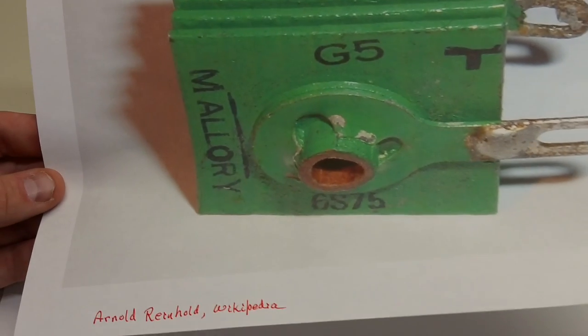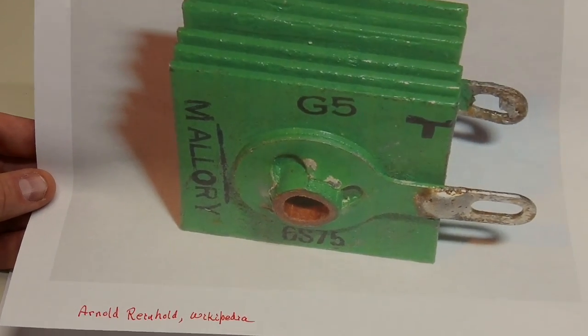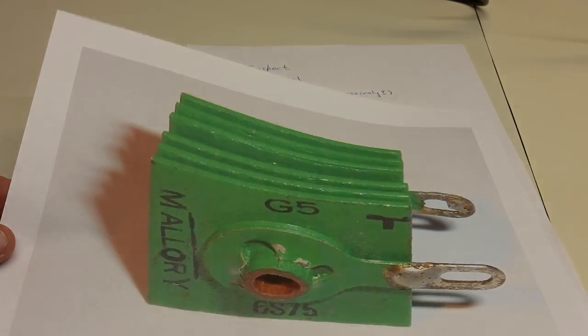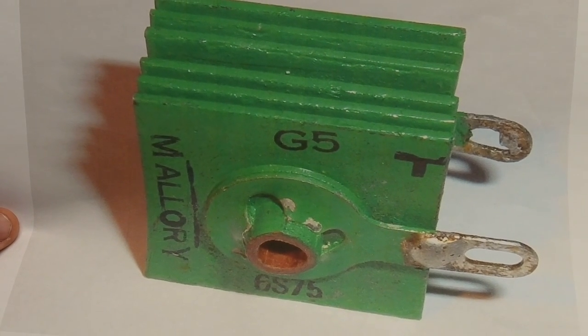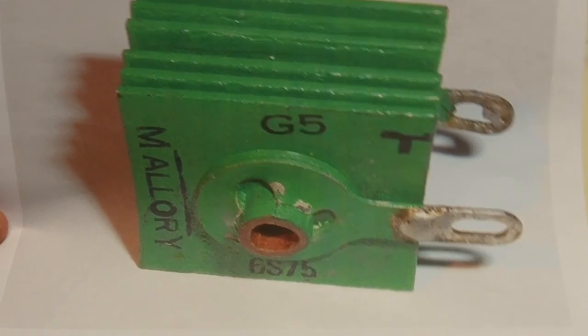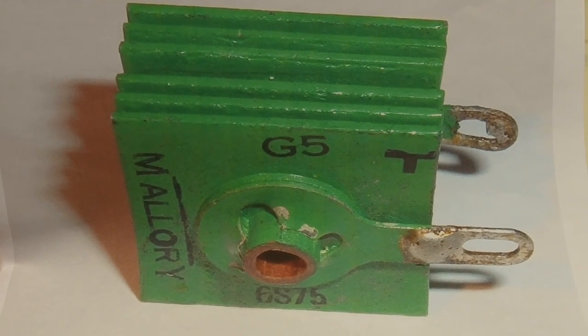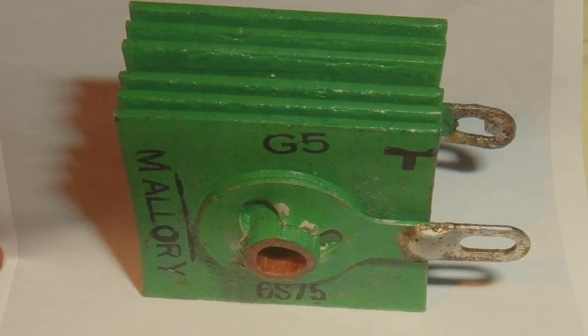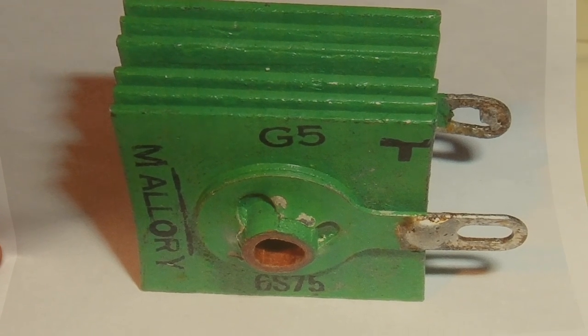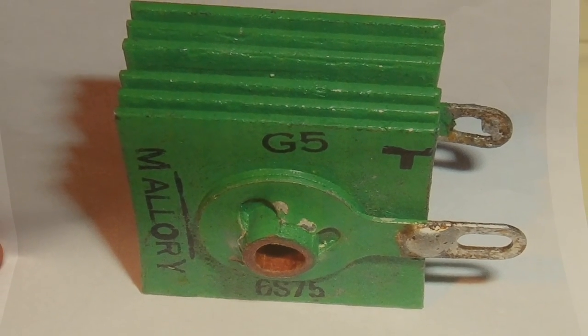Another thing in the power circuits that you need to be aware of are the use in older equipment of selenium rectifiers. These generally haven't been used since the early 1960s, but they do show up in some older equipment. If you don't know what a selenium rectifier looks like, here's a picture from Wikipedia. You can see that it looks somewhat like a stack of metallic postage stamps. Sometimes they're circular, like pancakes, but usually they're square. And the dimensions here are about 1 inch by 1 inch.